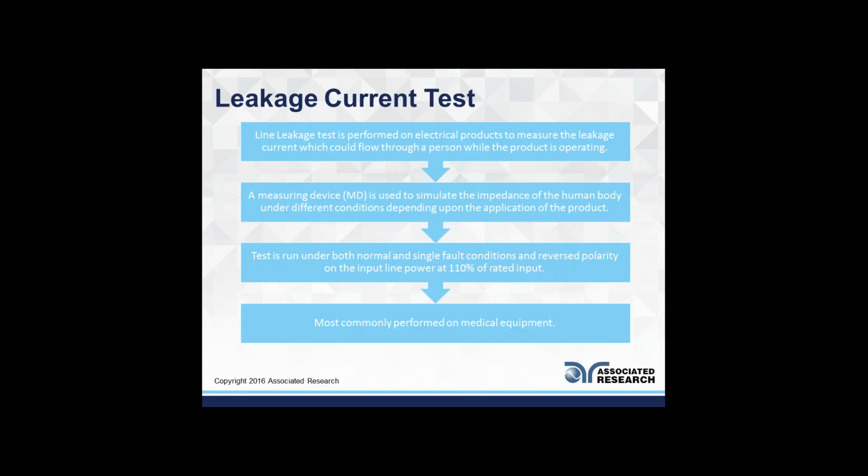So some of these numbers do come from the standards. Depending on the standards you're complying to, they will list the required acceptable amount of current that could be on your ground point or ground wire. And this is actually your testing.